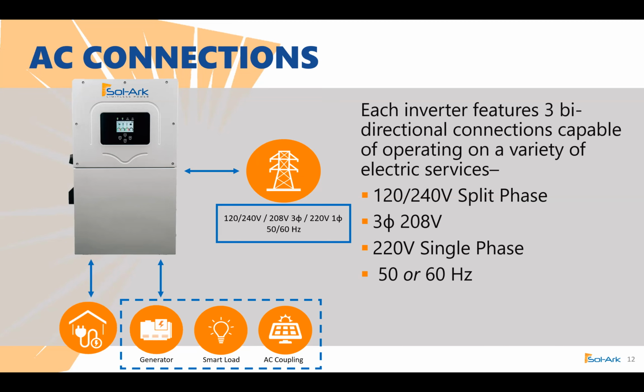They come standard at 120/240 split phase for your normal house in the USA here. We can also do 208 3-phase. If you stack multiple inverters, you can actually do an even balanced 208 3-phase if you stack 3. If you do 2, you can get unbalanced 208 3-phase. And if you do a single inverter, you can get 2 of the 3 legs, so you can still operate on 3-phase as well. And then maybe you do have a unique situation installing somewhere in the Bahamas, Africa, Europe. We can do 220 volt single phase on 50 hertz if need be. But we always operate default at 60 hertz.